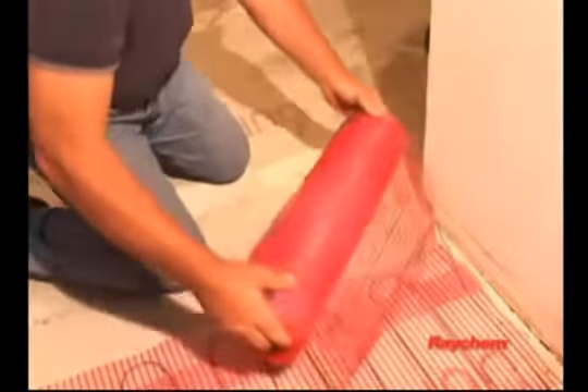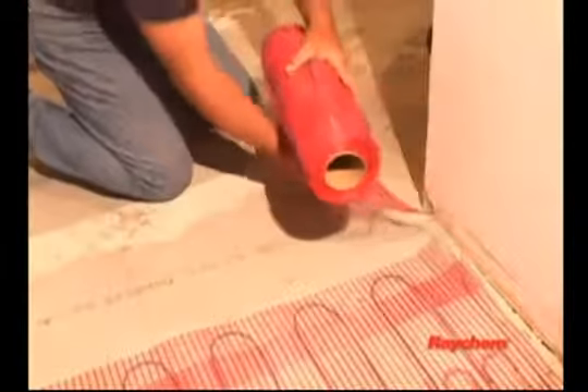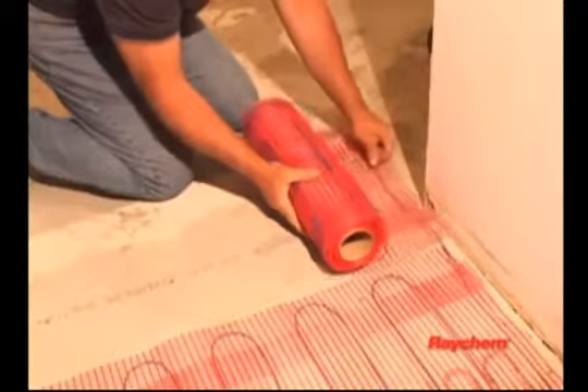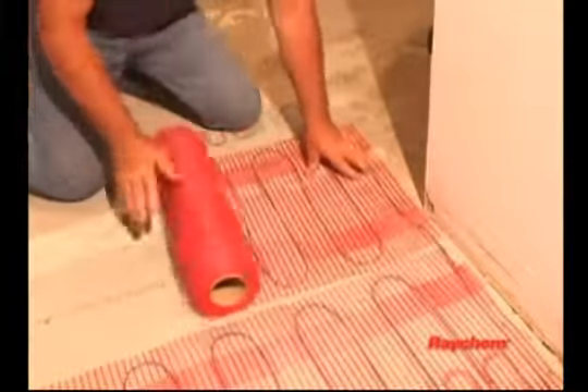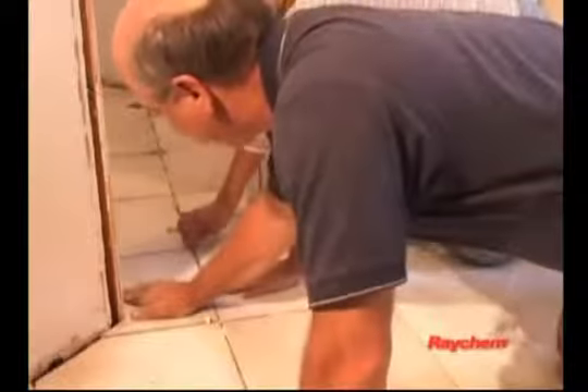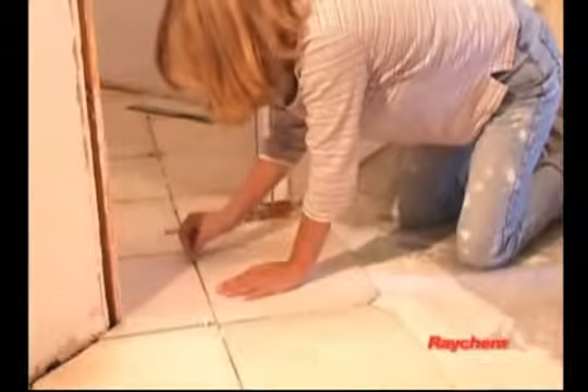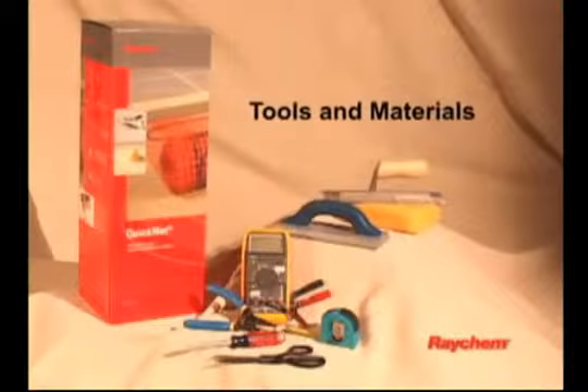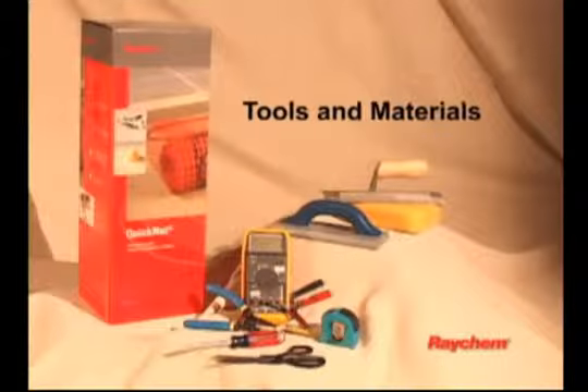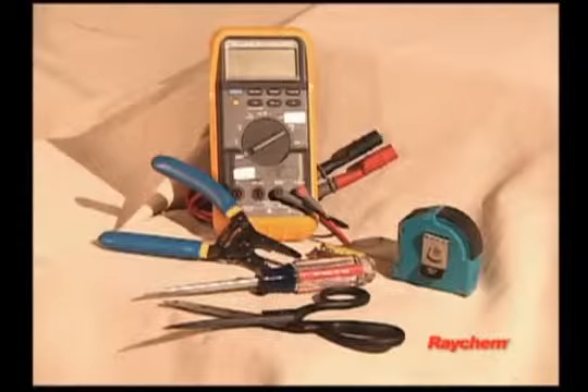Do not step directly on or damage the heating cable during installation. Do not install the QuickNet mat across expansion joints. Follow the manufacturer's instructions for installing the mortar bed, thin-set mortar, tile, and natural stone. You will require the following items to install and test the floor warming system: scissors, utility knife, wire strippers, tape measure, screwdriver, multimeter with clip leads.